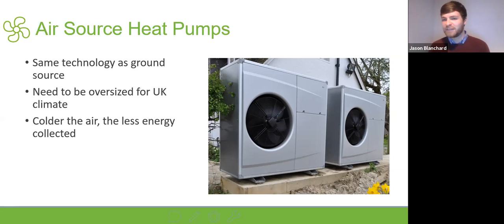The reason they're slightly less efficient is because, rather than taking energy out of a constant source of temperature like the ground - which doesn't vary much in temperature over the year - or water, which is constantly replenished with energy, air temperature changes drastically, as I'm sure you'll be aware if you've been outside today. So it's about sizing them correctly and accepting that they won't be as efficient as ground source year round, but if sized correctly, they can be quite close to just as good as ground source, at a significantly lower cost.